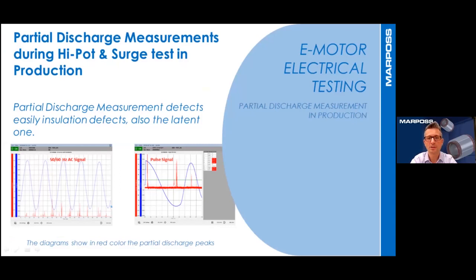The measurement of partial discharge runs concurrently with the hipot test and surge test. They require no additional test time and allow finding defects also where the standard test doesn't detect any variation. The only way to detect the latent defects without a test of partial discharge would be to apply a very high voltage in order to perforate the dielectric of the insulation wire, generating a big discharge that is detected by the standard test. But this method causes very high stress to the stator windings, with negative effects on the electric motor life. With the partial discharge measurement, 100% of latent defects are detected, applying a much lower voltage, generating no stress to the windings.